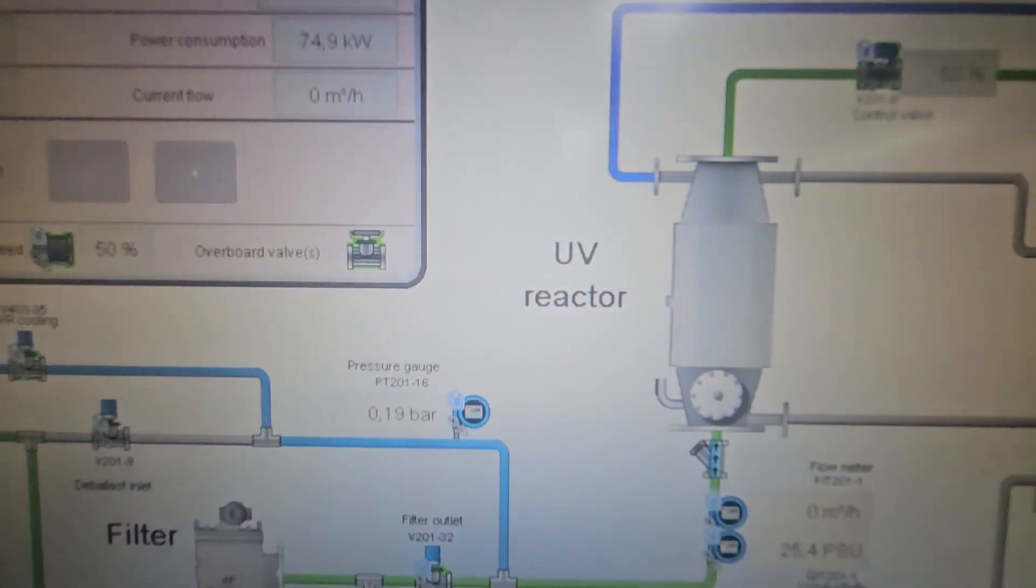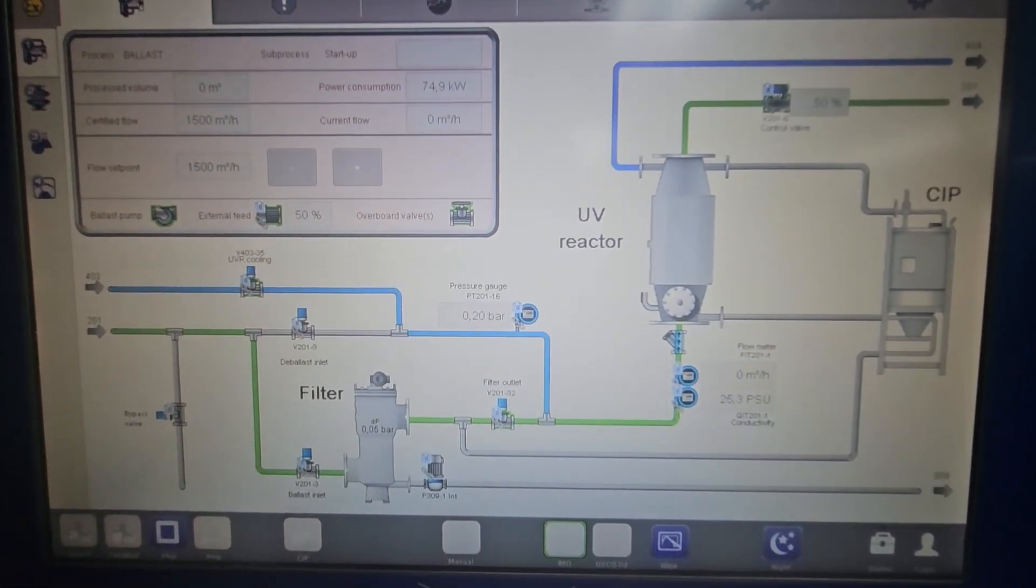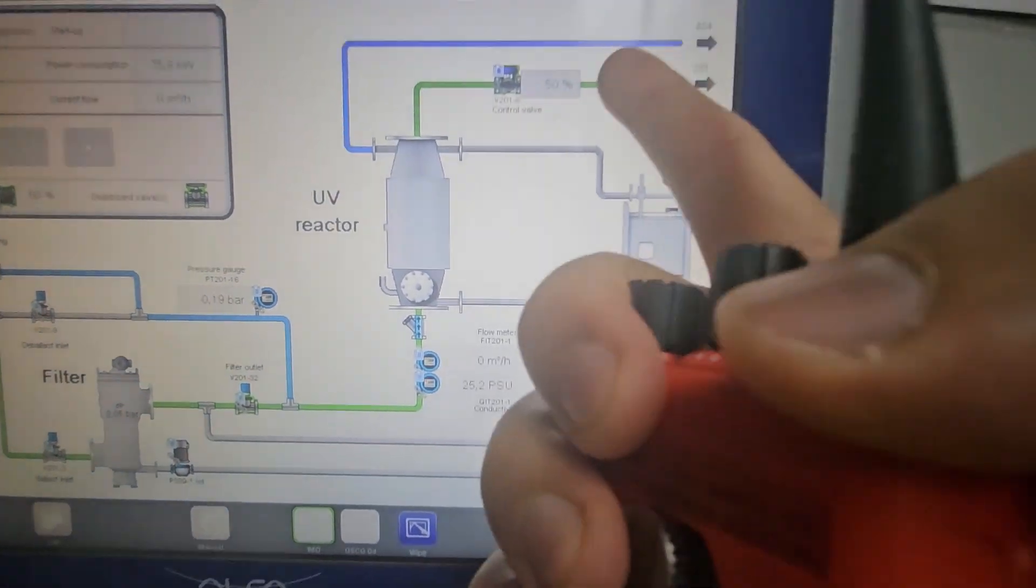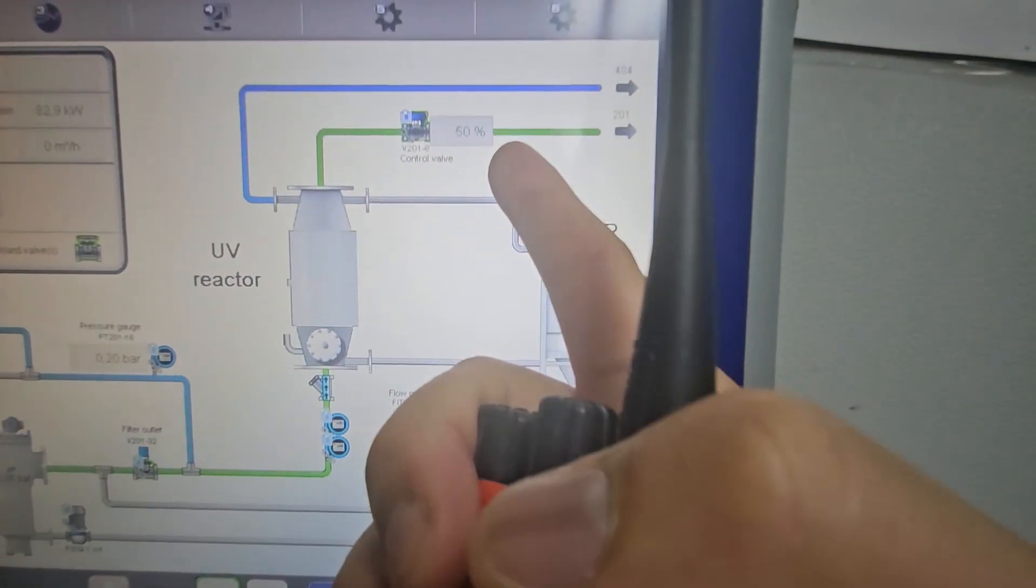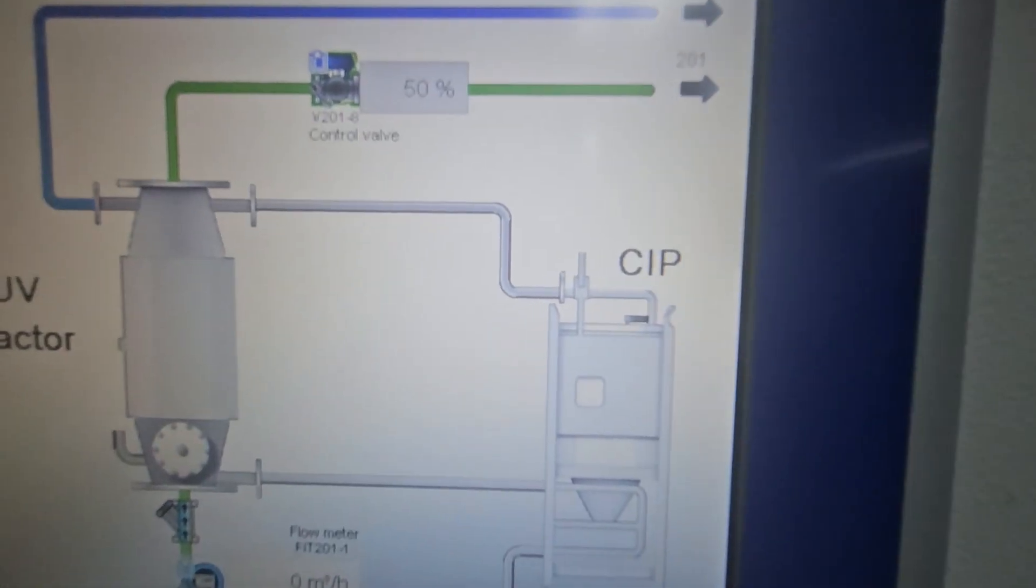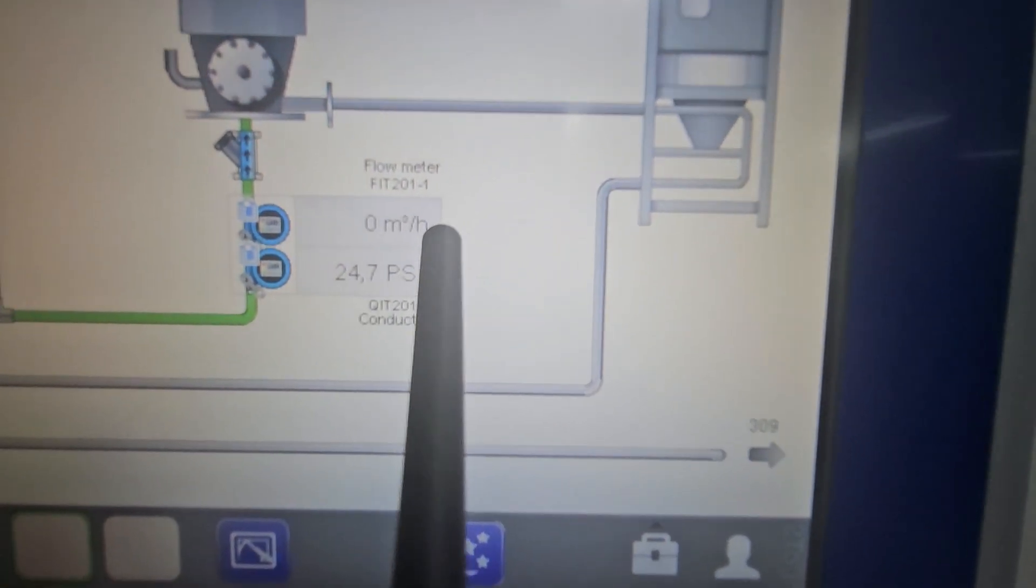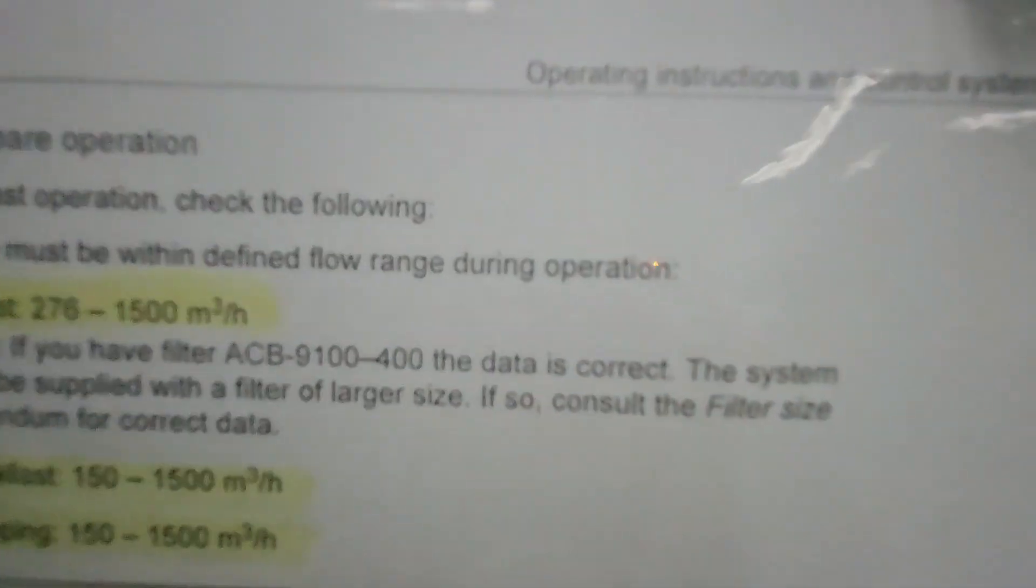Then you will see gradually that this control valve will open up to 100%, and you will see also the flow meter here will increase as per requirement. Whenever you are ballasting, it should be within 276 to 1,500 cubic meters per hour.